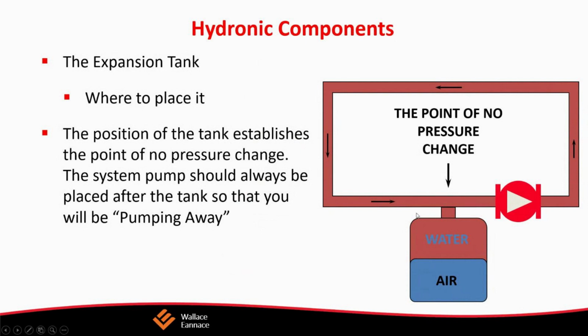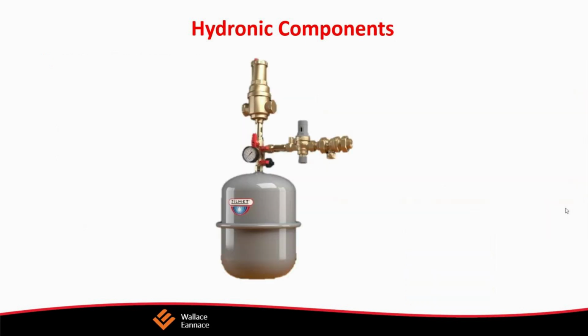The bladder tanks, as you can see here, basically have a bladder inside the tank. It can expand to the size of the tank. Bladders can be full acceptance, where the volume of fluid it will hold is equal to the volume of the entire tank steel shell, or they can be low acceptance bladders, where the bladder can hold less than the steel shell, and it's used where safety and system pressure are a large concern.